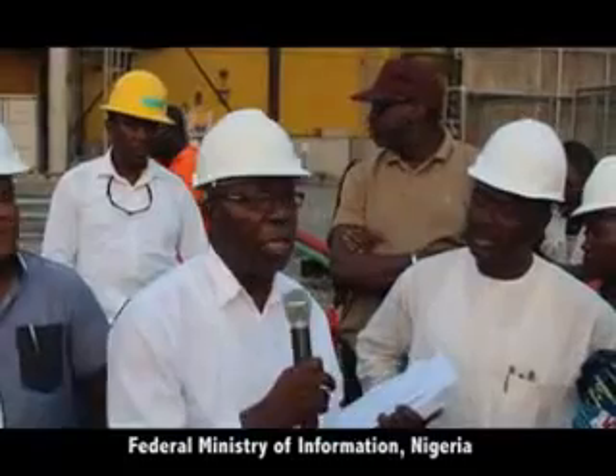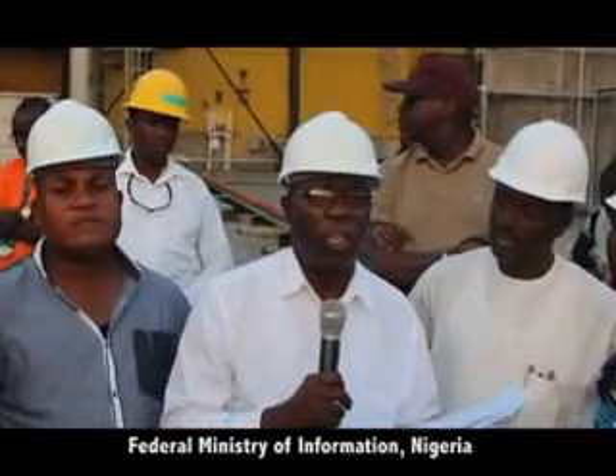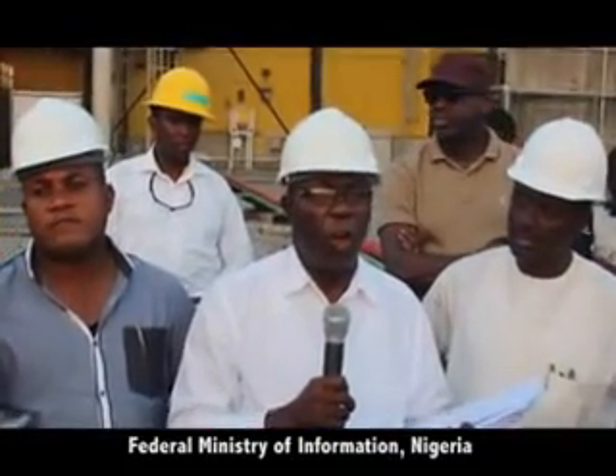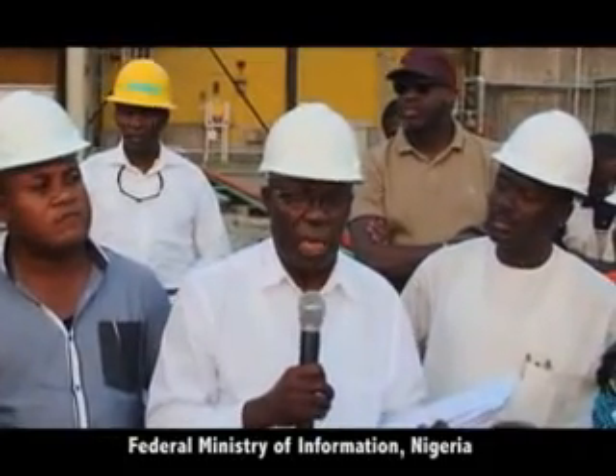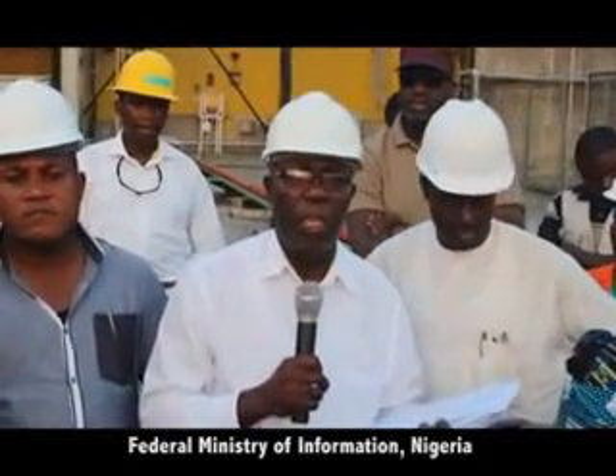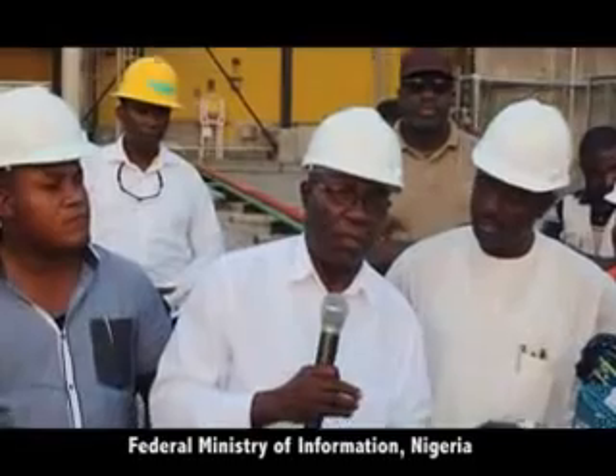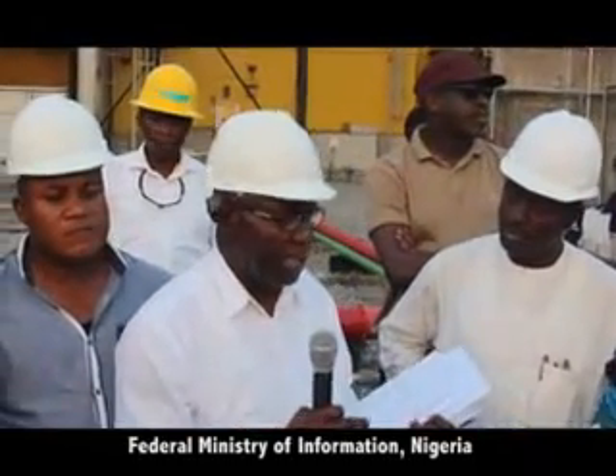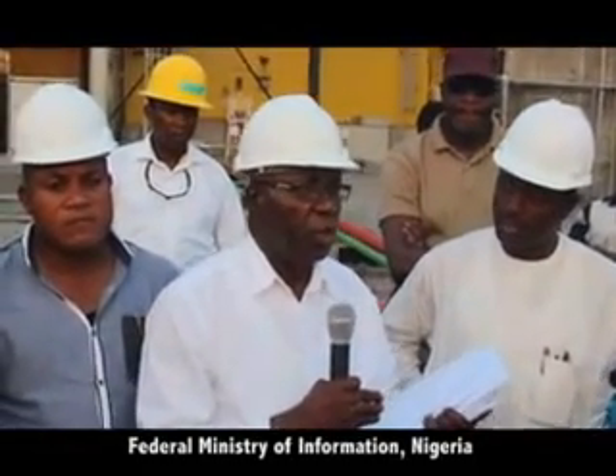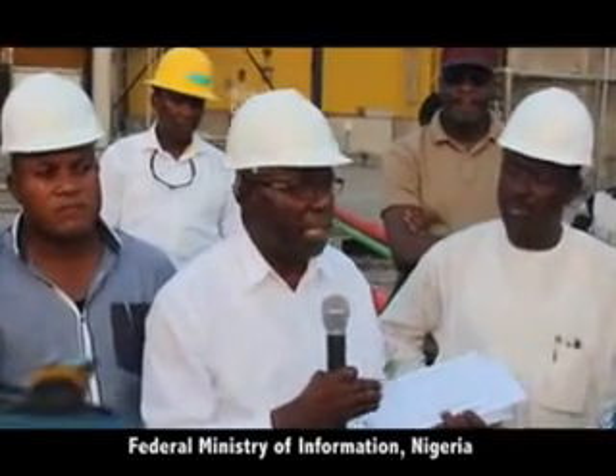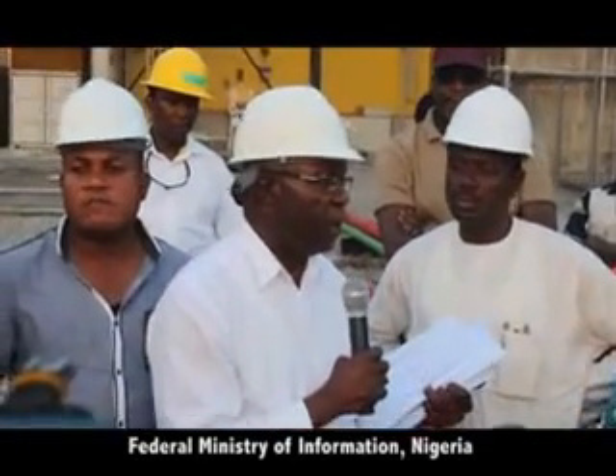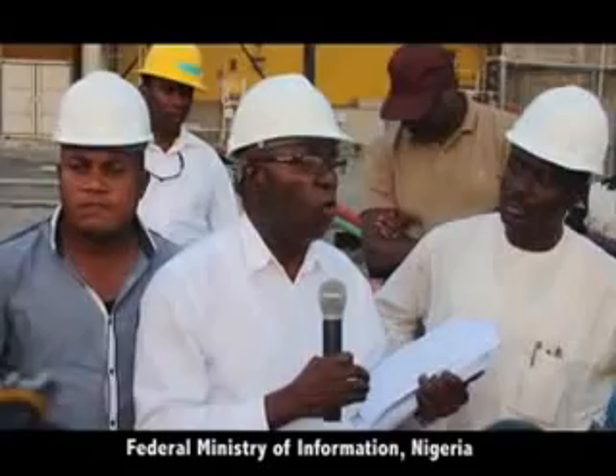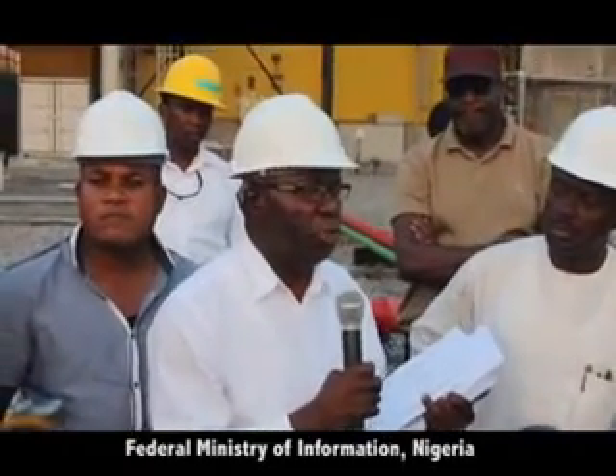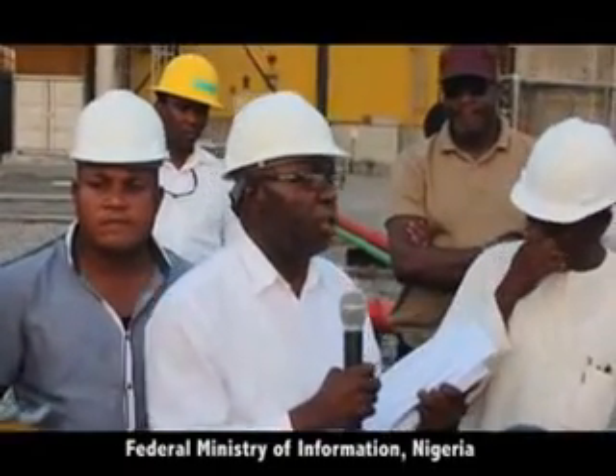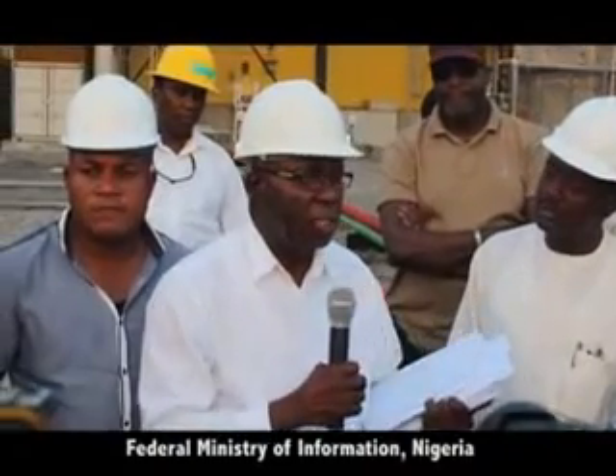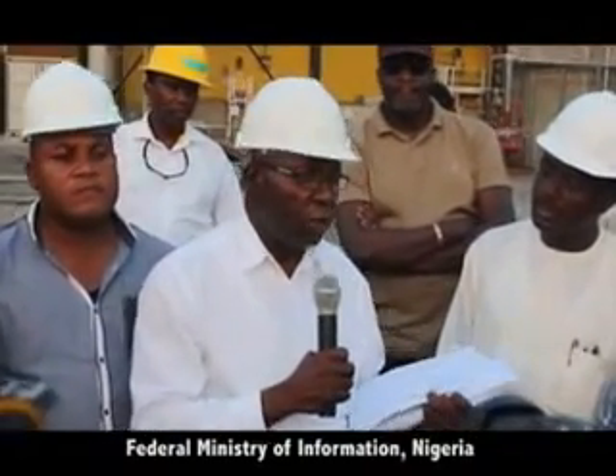What's the issue? The issue on Unit 3 was the foundation of what we call the surge arrestor foundation. At completion of the foundation, it was collapsing, there was a subsidence. Because of this, all the mechanical and electrical tests have been performed and confirmed okay. The unit was then shut down to address the issue of the subsidence, and it has been addressed. We are now going back to rerun the unit.